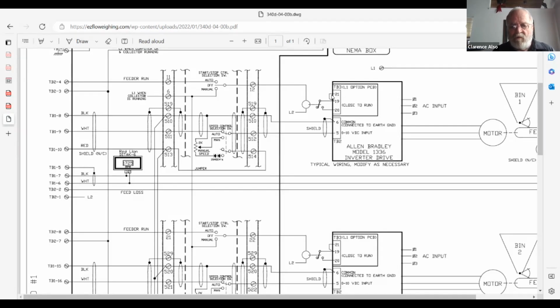So if we're telling this thing to run, this is going to have a 0 to 10 input, this is the speed input. Here we get some run input, here's a speed input. So it says, okay, if you've got 5 volts, that means you want to go half speed. It's going to tell this VFD we want it to go half speed, and that motor goes at half speed. These are the kind of things you can start putting together on your own as you learn this maze.